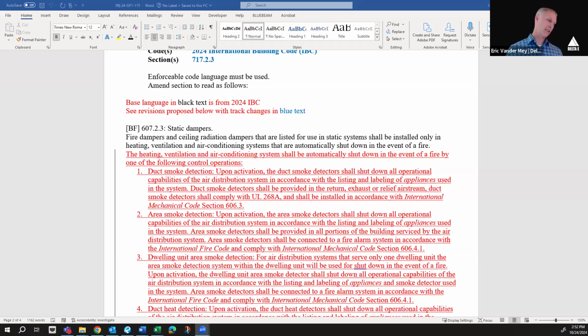Before we go into these in detail, there are two types of dampers, the static ceiling radiation dampers and the dynamic dampers. Some of the provisions showing up in the code are coming from the dynamic ceiling manufacturers. The static dampers are much more readily available; multiple manufacturers make those, and these dampers are very specific around the UL listings. For dynamic dampers, there are only one or two manufacturers.